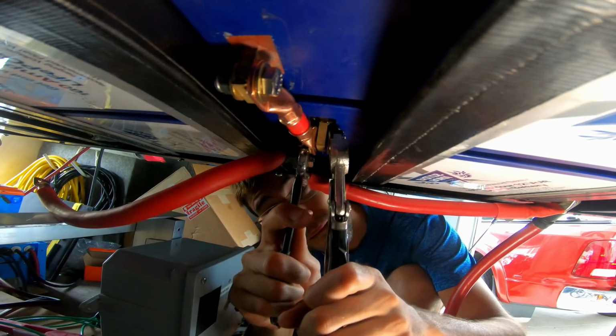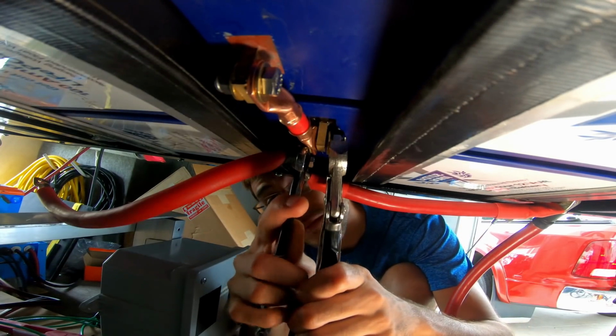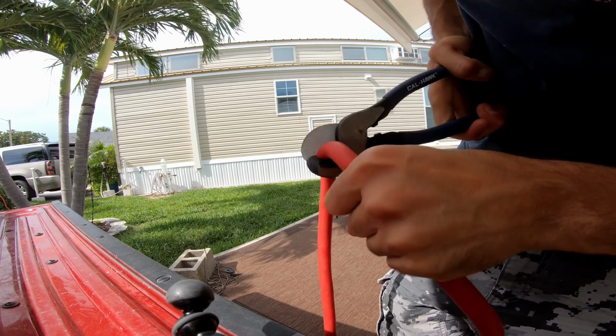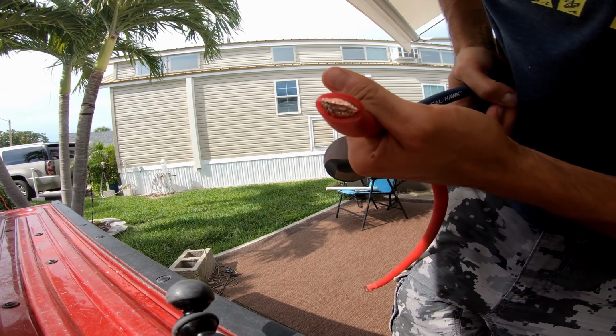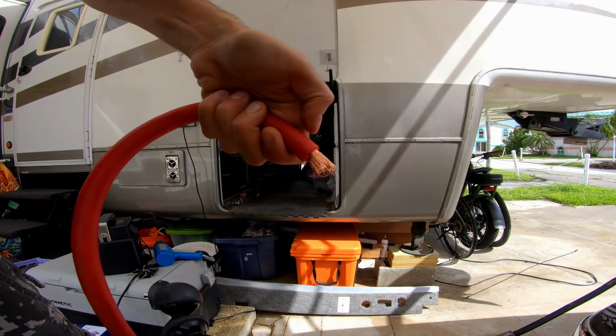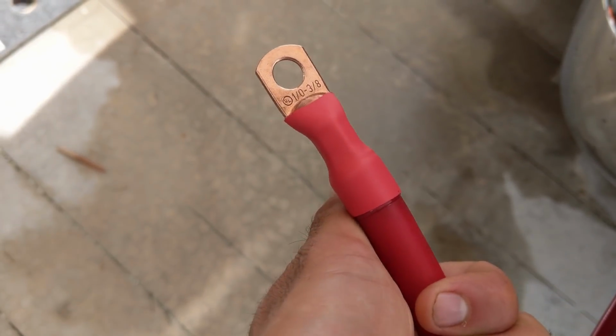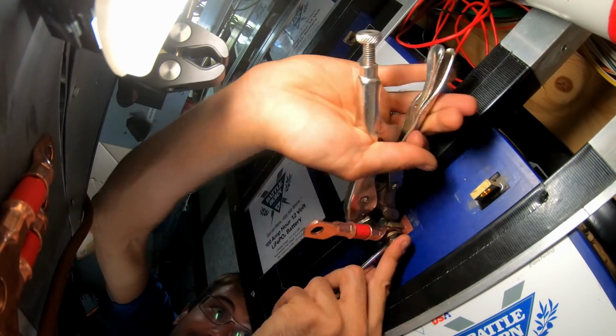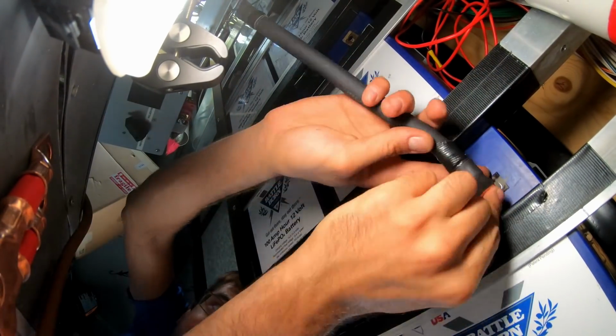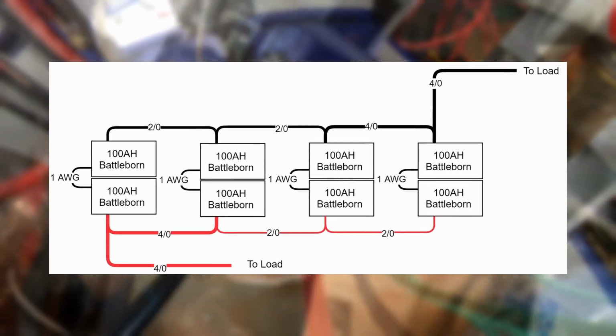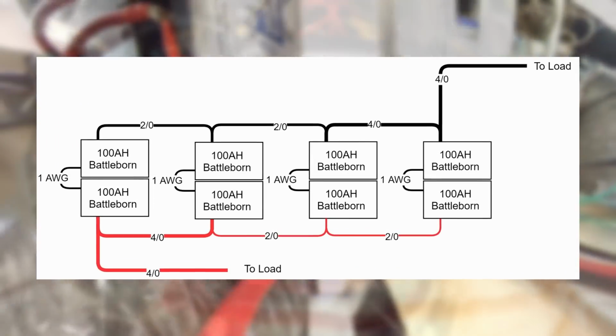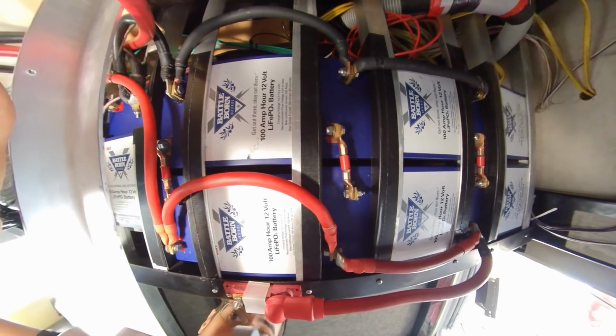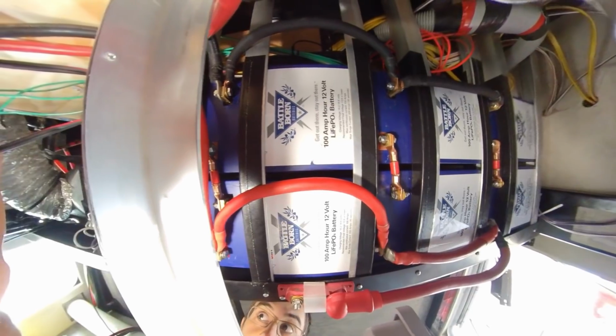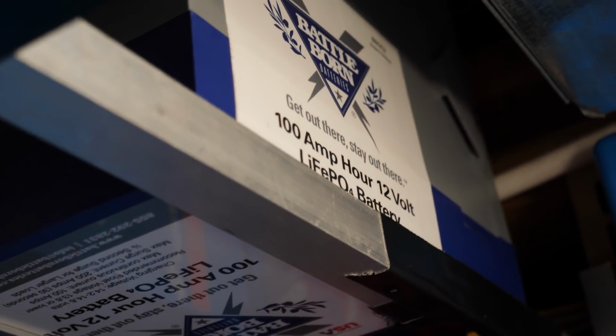And we decided to stick with 24 volts because with the amount of solar that we were installing, this is about the lowest voltage we would want to run because it halves the current over a 12-volt setup, allowing us to use smaller wires, less charge controllers, and enjoy higher efficiencies overall. We wired the batteries using a combination of 1-gauge, 1-aught, and 4-aught cable depending on where the cables were installed, as current is cumulative in a battery pack. And by calculating the expected currents, we were able to work with smaller gauge cables in some tight spaces.